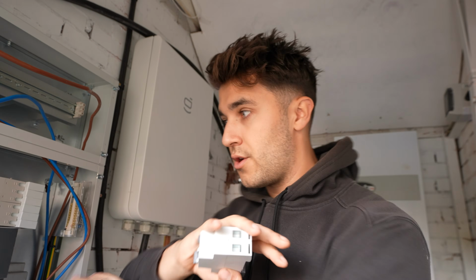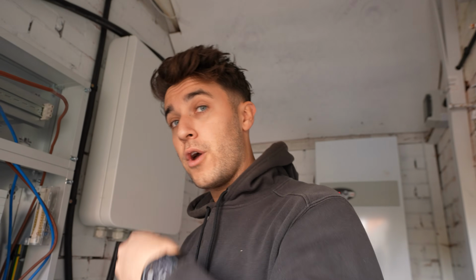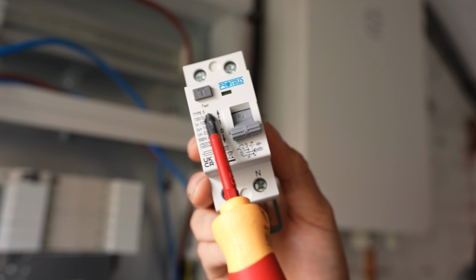We want to try and achieve discrimination. So if in the house or any of the other buildings, they have a 30 milliamp RCD that is operating at the same time as this, then that would be a nuisance. You could have a nice RCBO board, but if this is tripping every time one of your circuits trips, it's going to knock out the whole property. They'll have to walk over to their plant room and reset this RCD, which is a right pain. So you don't want that. To achieve discrimination, you want to use a type S.